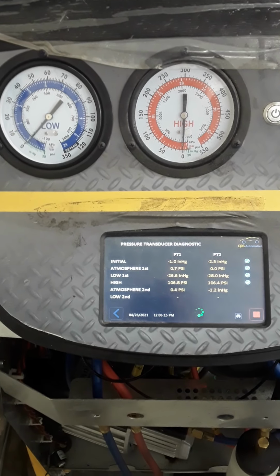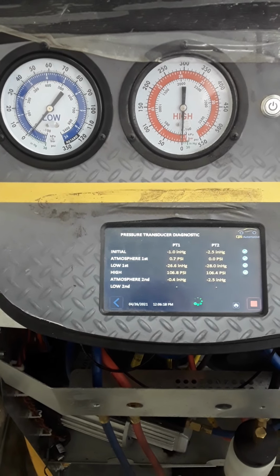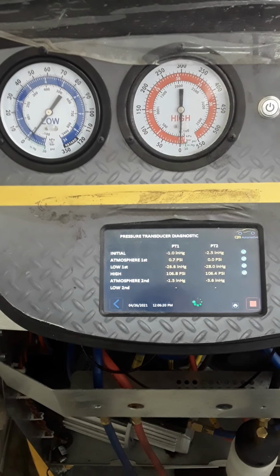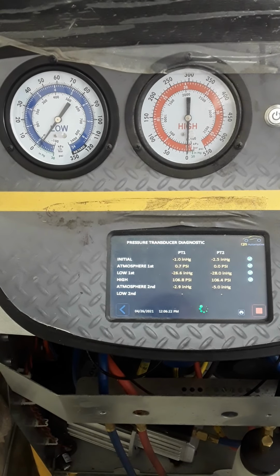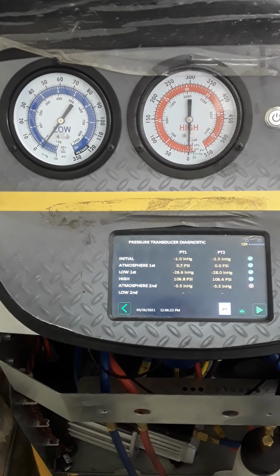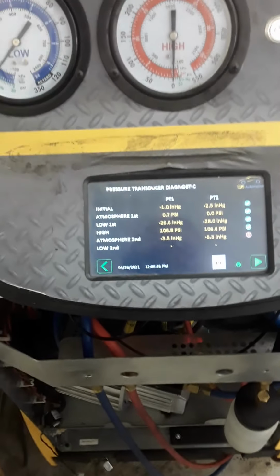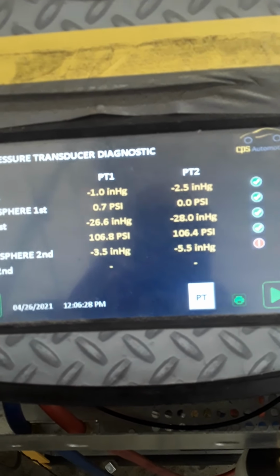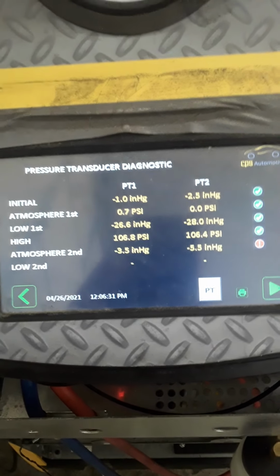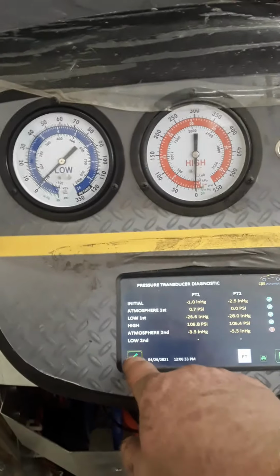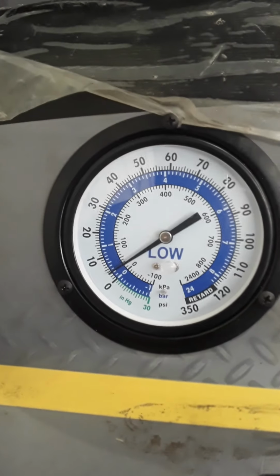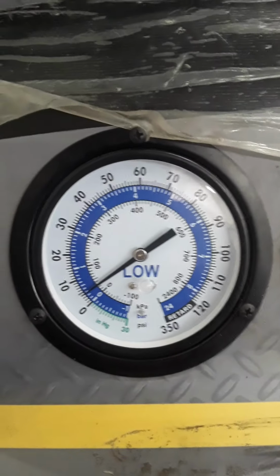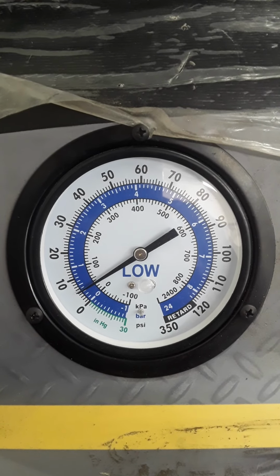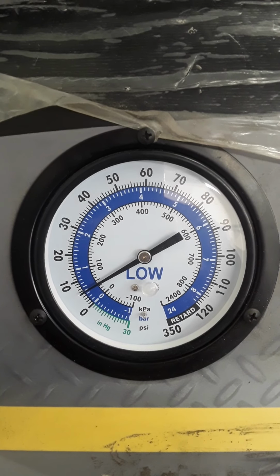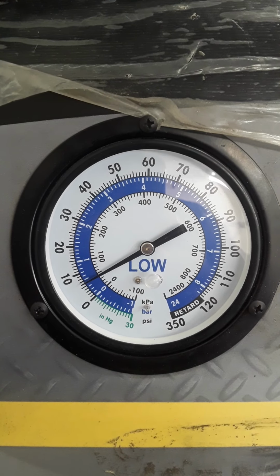I'm going to tell you, that diagnostic you're going through right now, I never do that. It's just a waste of time. He's calibrating the pressure transducers the other way. It just failed on the diagnostic on atmosphere 2. Let's do this. I just want to try to calibrate it one time, because I think I know what your problem is. It's that brass fitting. If you replace that cylinder, your problem doesn't go away.